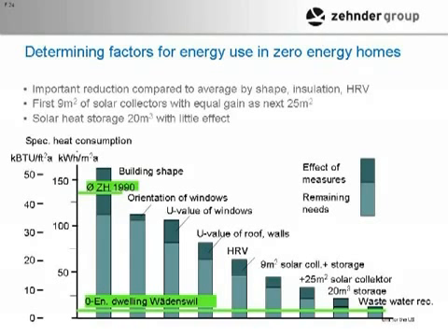Then he used solar collectors, and you can see 9 square meters of solar collection brought you down this step, and then an additional 25 square meters of solar collection brought you an equivalent down. So the first 9 meters get just as much as an additional 25 meters. What that worked out to is that small panel was able to heat enough water to keep the house warm on most days. And the extra 25 meters only got you the additional that you needed on the real cold days, on cold stretches. All right?